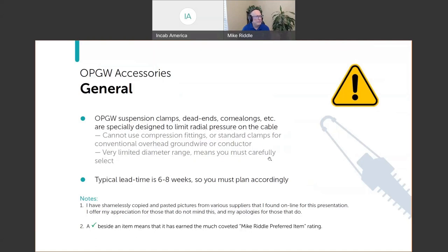And you can't even use standard clamps like pistol grips for conductors. Even standard suspension shoes are not suitable for use on OPGW, the ones that you would use on conventional overhead ground wire or conductor. You have to use accessories that are specifically designed for use on OPGW.